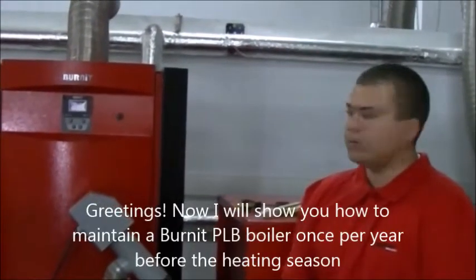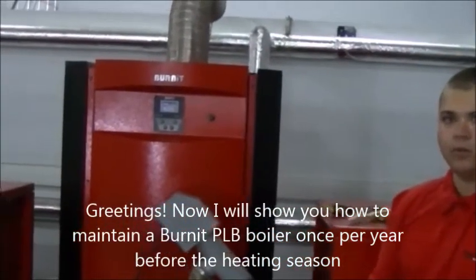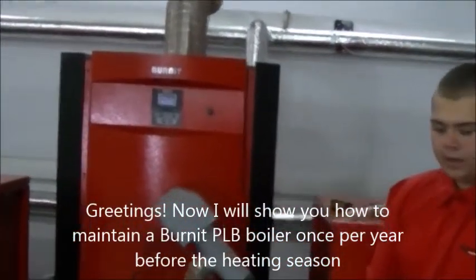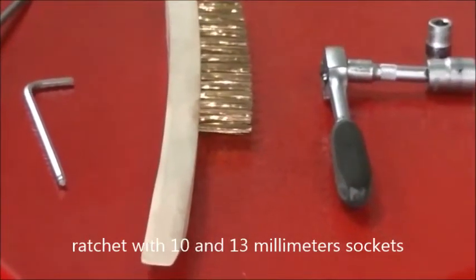Greetings. I will show you how to maintain a Burnit PLB boiler once per year before the heating season. We will need a vacuum cleaner, screwdriver, 4mm hex key, hard brush, and a ratchet with 10 and 13mm sockets.